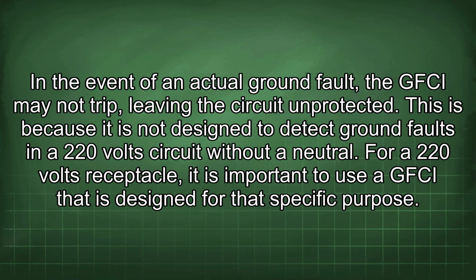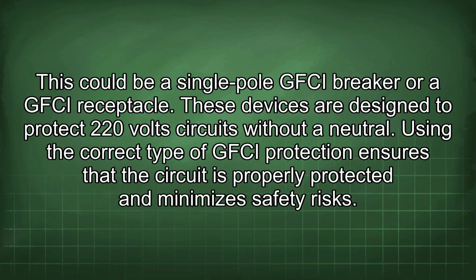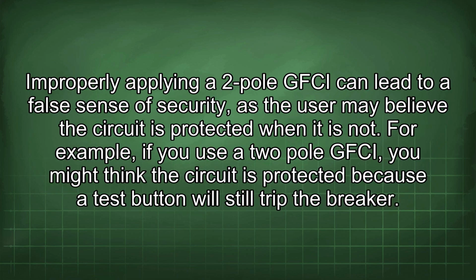For a 220-volt receptacle, it is important to use a GFCI that is designed for that specific purpose. This could be a single-pole GFCI breaker or a GFCI receptacle. These devices are designed to protect 220-volt circuits without a neutral. Using the correct type of GFCI protection ensures that the circuit is properly protected and minimizes safety risks. Improperly applying a two-pole GFCI can lead to a false sense of security, as the user may believe the circuit is protected when it is not.